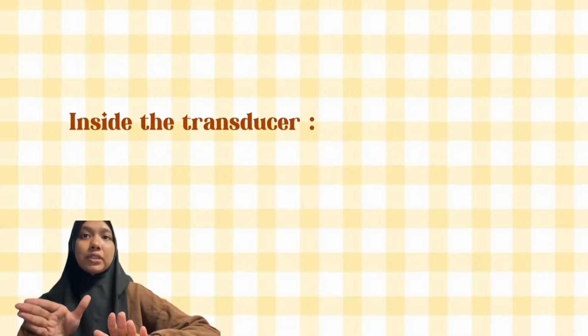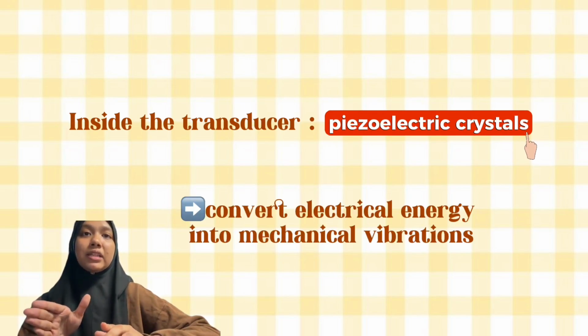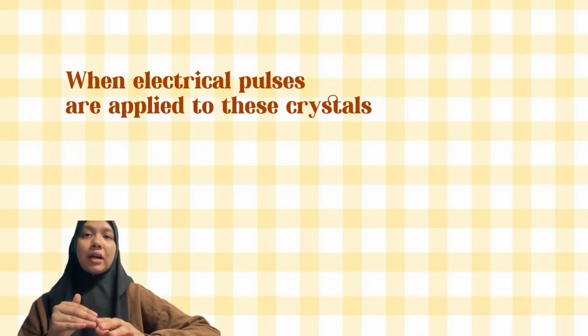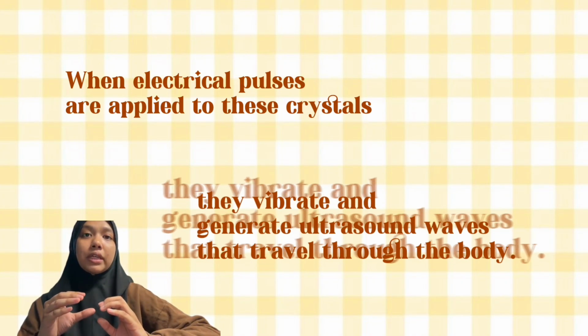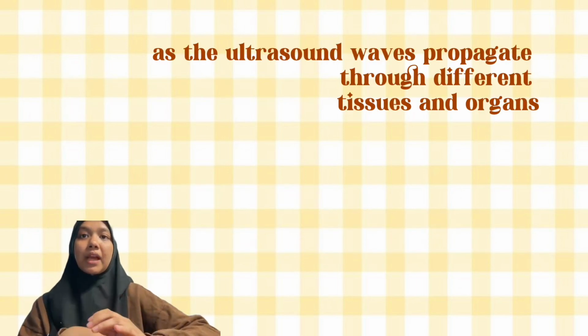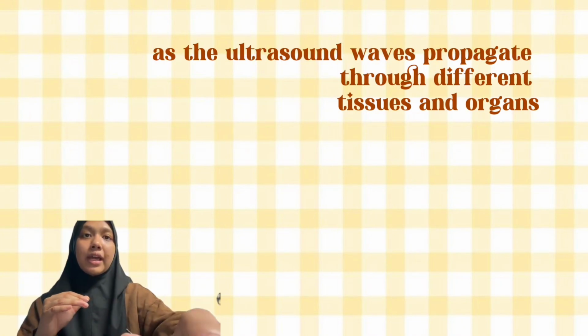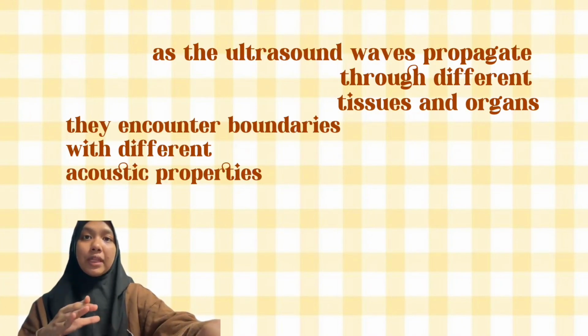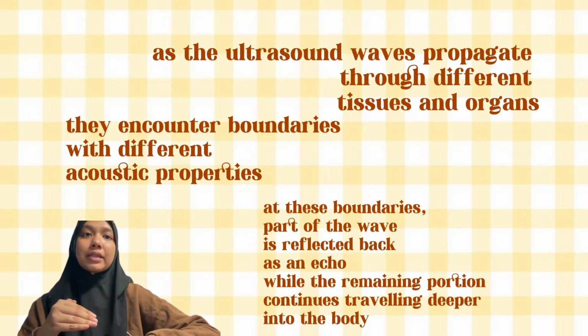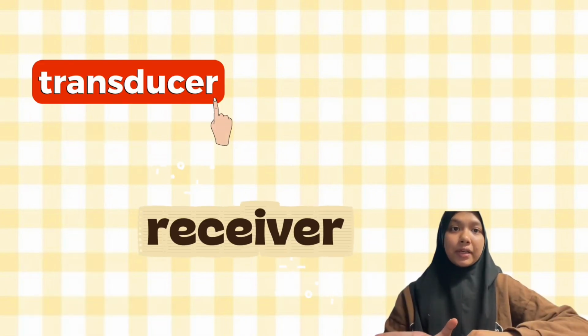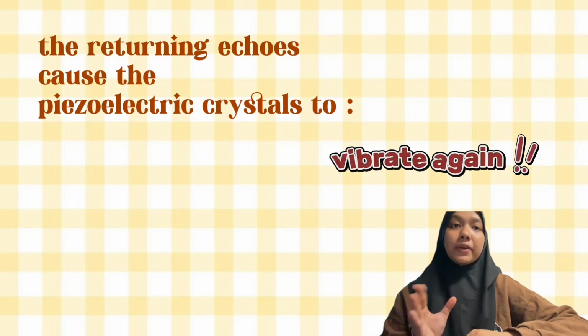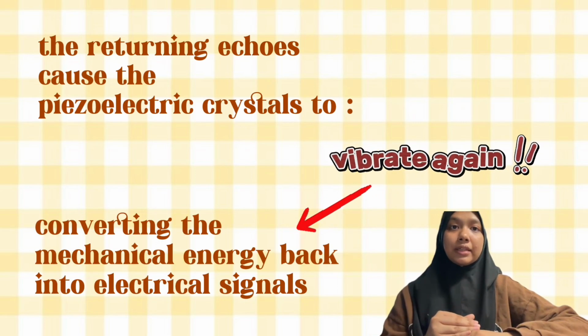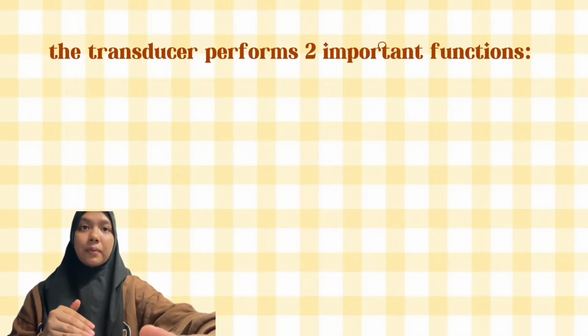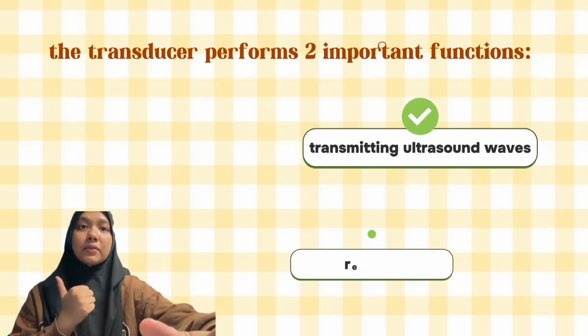The operation of an ultrasound system begins with the piezoelectric effect. Inside the transducer are piezoelectric crystals that can convert electrical energy into mechanical vibration. When electrical pulses are applied to these crystals, they vibrate and generate ultrasound waves that travel through the body. As the ultrasound waves propagate through the different tissues and organs, they encounter boundaries with different acoustic properties. At these boundaries, part of the wave is reflected back as an echo, while the remaining portion continues traveling deeper into the body. The transducer acts as a receiver. The returning echo causes the piezoelectric crystal to vibrate again, converting the mechanical energy back into an electrical signal. Therefore, the transducer performs two important functions: transmitting ultrasound waves and receiving reflected echoes.